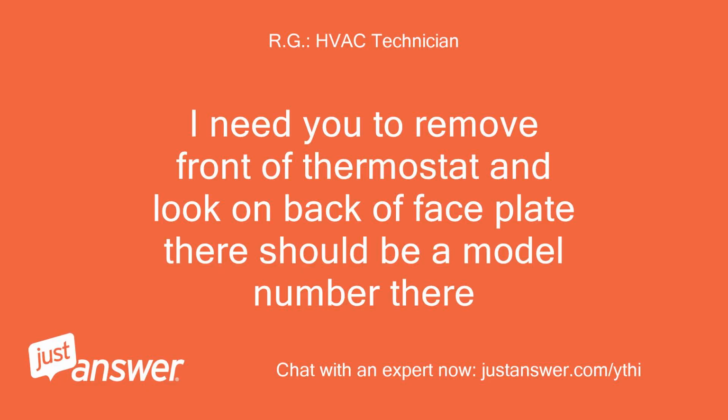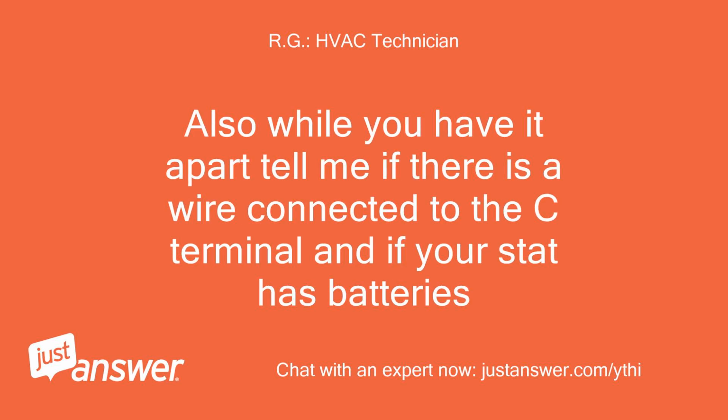I need you to remove the front of the thermostat and look on the back of the face plate. There should be a model number there. Also, while you have it apart, tell me if there is a wire connected to the C terminal and if your stat uses batteries.